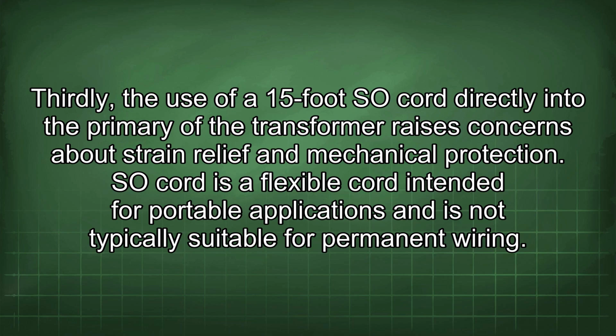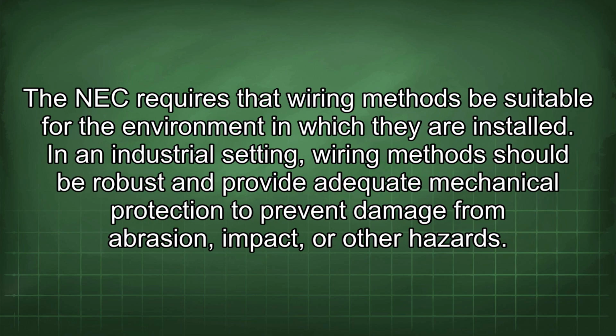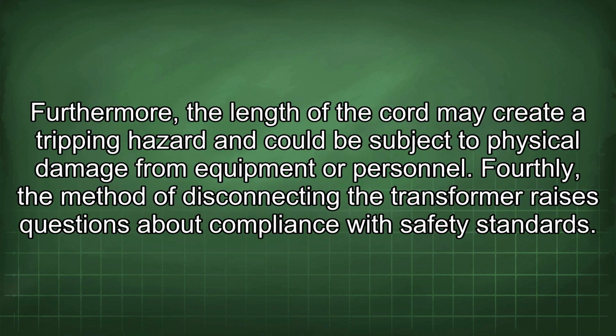Thirdly, the use of a 15-foot SO cord directly into the primary of the transformer raises concerns about strain relief and mechanical protection. SO cord is a flexible cord intended for portable applications and is not typically suitable for permanent wiring. The NEC requires that wiring methods be suitable for the environment in which they are installed. In an industrial setting, wiring methods should be robust and provide adequate mechanical protection to prevent damage from abrasion, impact, or other hazards. Furthermore, the length of the cord may create a tripping hazard and could be subject to physical damage from equipment or personnel.